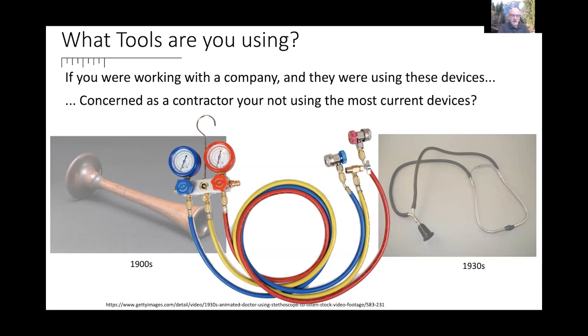If you didn't vet and clean out these lines, you're allowing refrigerants to get out. Imagine every service call, the hoses are filled with refrigerant, and of course, I always release my lines -- well, that's not a good thing either. The new probes out there are small; they don't actually hold refrigerant, they don't have the hoses or tubes anymore, so we don't have that problem. These are some of the things we're vetting.